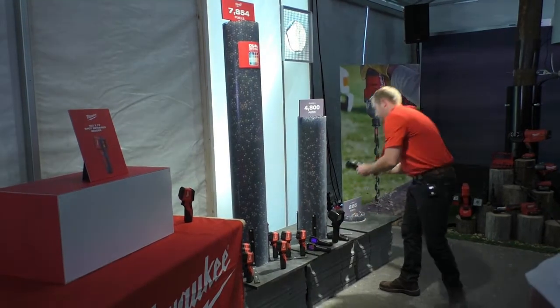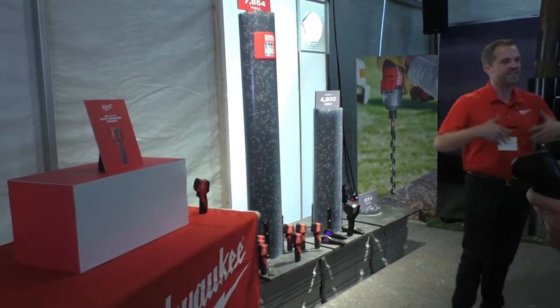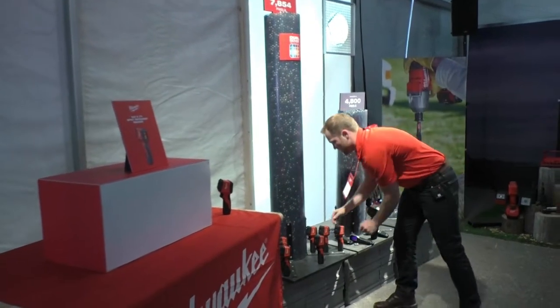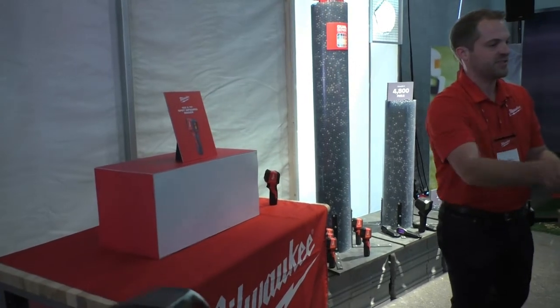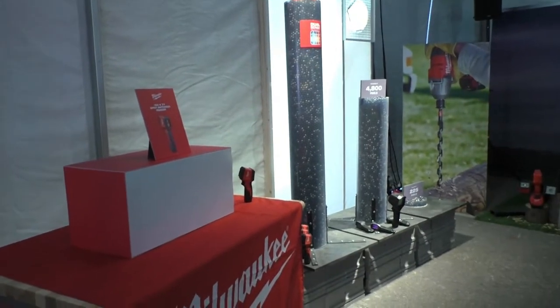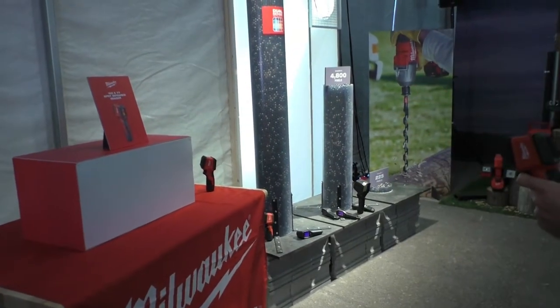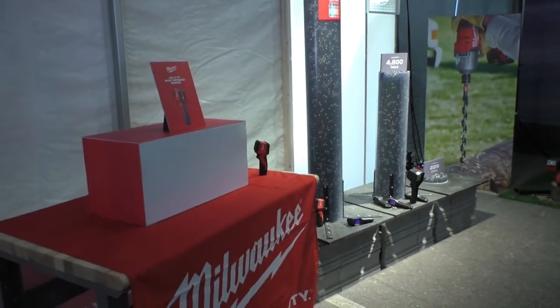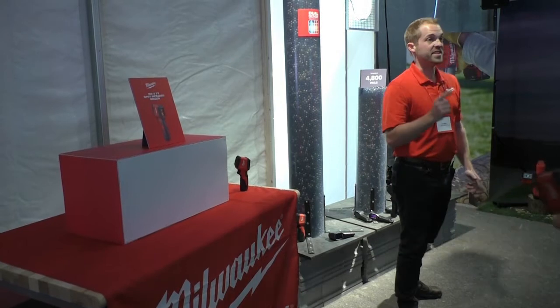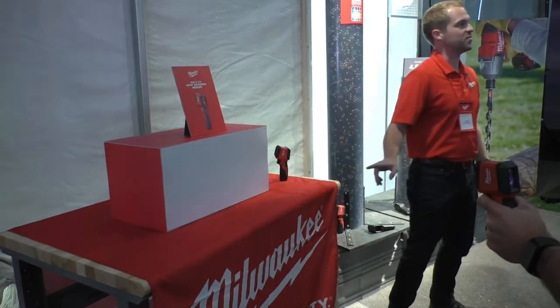So then you step up — now we get a couple more pixels, you're up to 4,800. Now you're probably going to see some things inside that box that you couldn't see before, some definition starting to take place. But you're probably missing a couple things. With this one you're just going to press and hold the trigger to scan — keep passing these around. The image quality immediately is a lot higher. You're immediately able to see that it's the Milwaukee logo, and you've probably even picked up things you didn't see on the second camera — maybe some holes, some hot spots on the top, or even the ones on the bottom that still have some residual heat.